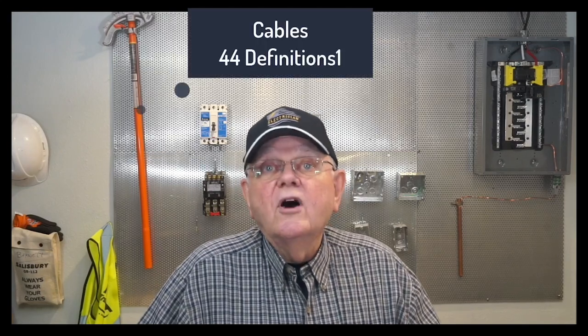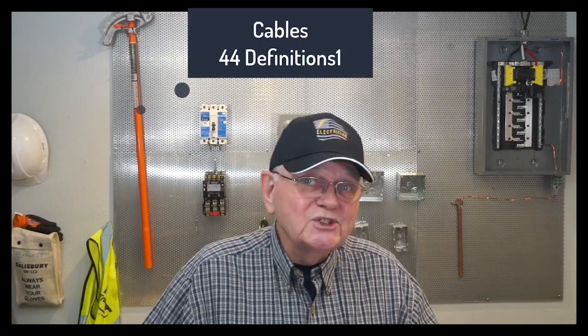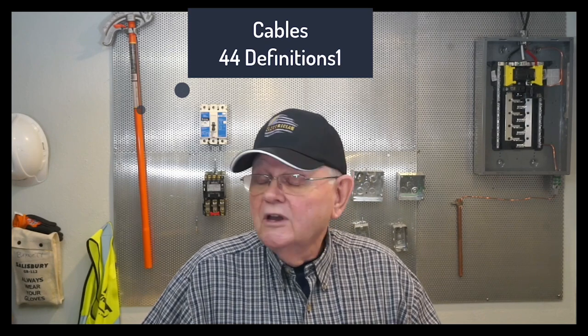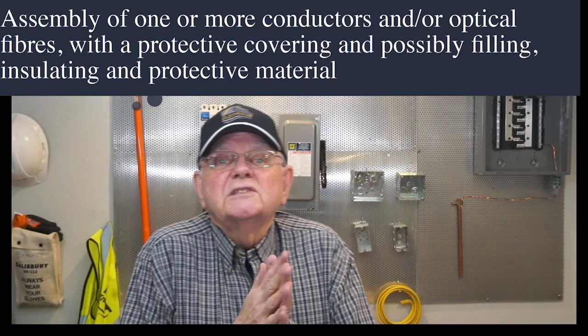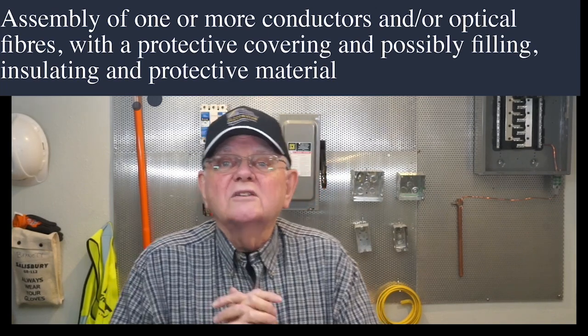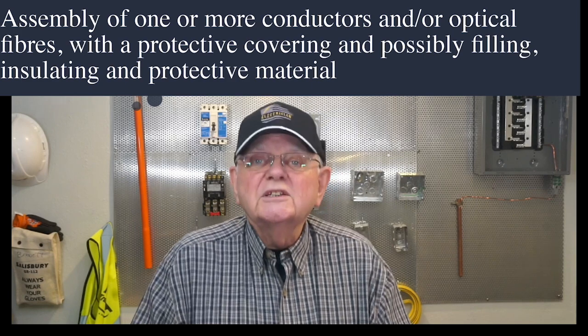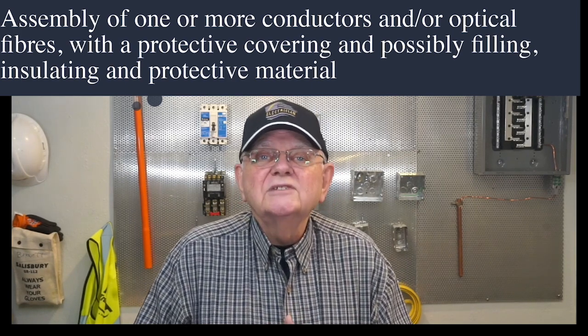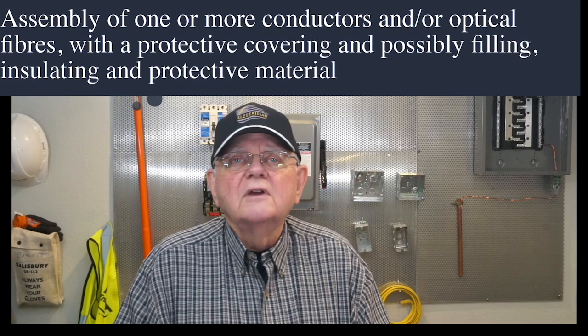We're going to look at some different cables next. There are 44 different definitions for cables in the NEC. We're for sure not going to go through all of those, okay? What's interesting is there is no definition for cable itself in the NEC. If we take a look at some specific definitions, like the IEC, which defines it pretty well, it says it's an assembly of one or more conductors or optical fibers with a protective coating and possibly a filling, insulating, and protective material. We'll talk about a couple more, but there are 44 different ones.